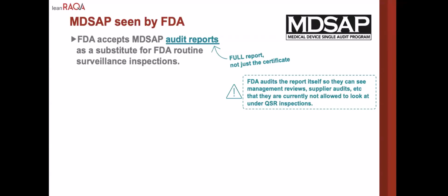Also, because they only accept the reports in lieu of FDA routine inspections, all FDA has to do is say that their audit is non-routine, and then they come in to do an inspection. I had a company that was based in Canada, so they had their MDSAP, and FDA came to see them fairly frequently, not necessarily on the 2-year, but despite them turning their audit report in, because they said, well, this isn't a routine inspection. This is a risk-based inspection.